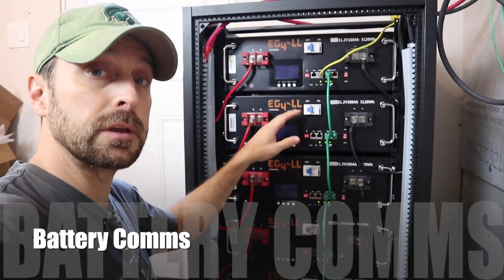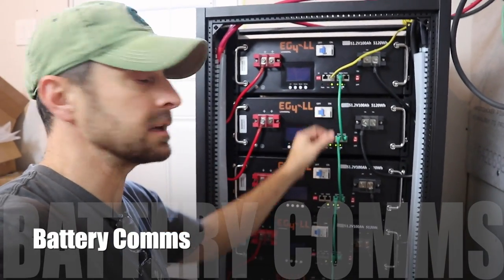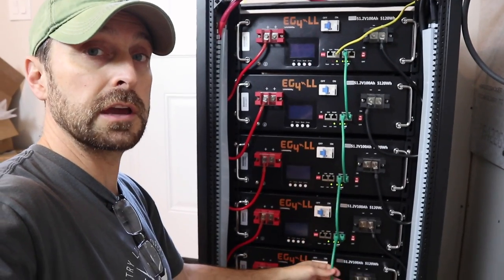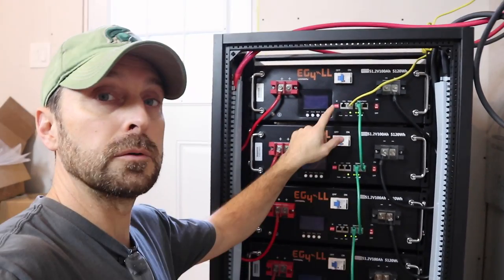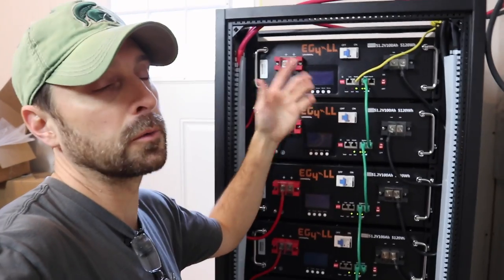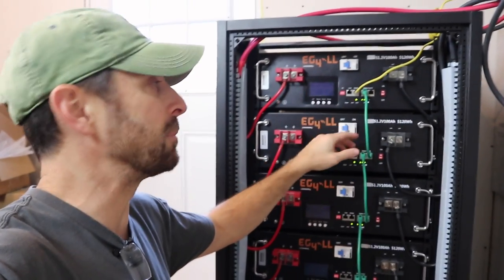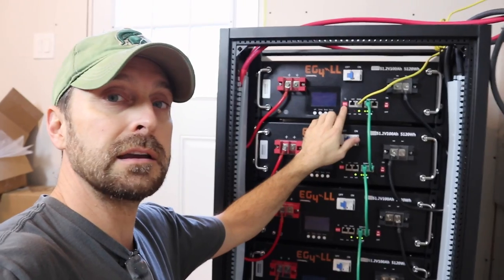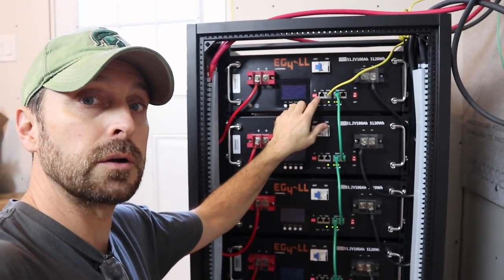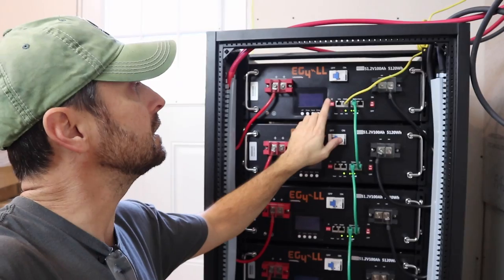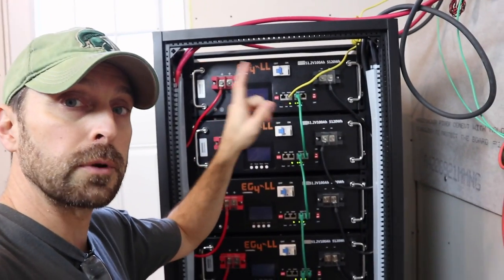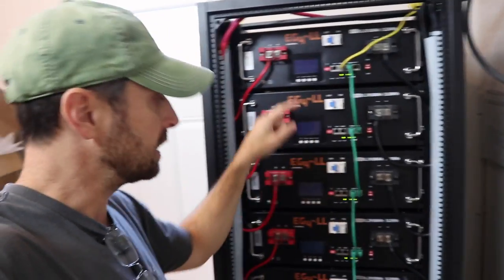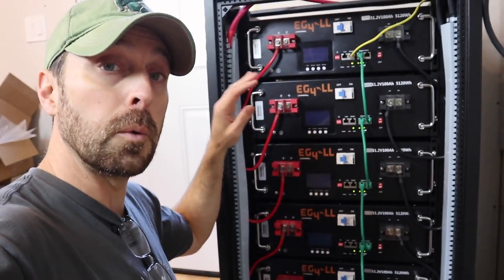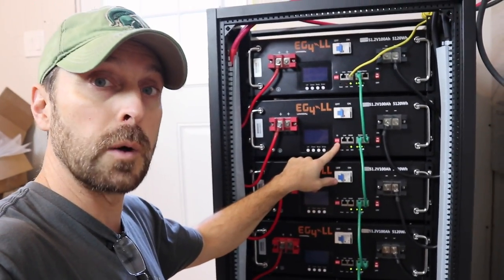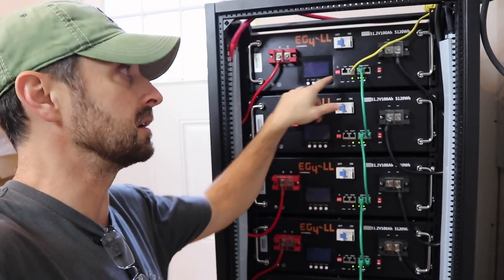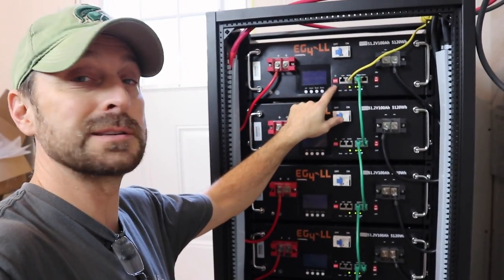So let's talk about our battery communication first. Each battery is talking to each other through these communication ports right here, through these little jumpers. Remember, your top battery, or whichever battery you set it at, but normally your top battery, the dip switches on the outside here are set to down, down, down, up. And that is so this battery can talk properly to the inverters. Each other battery on here can be set to whatever combination on the dip switch you want, as long as they don't match each other and as long as they don't match this top one, of course.